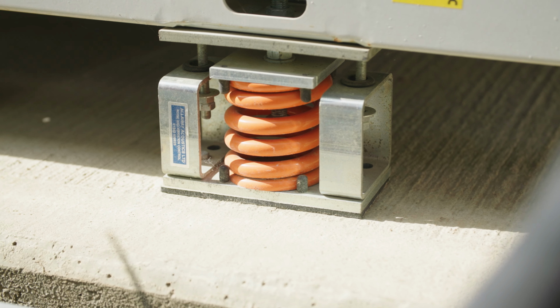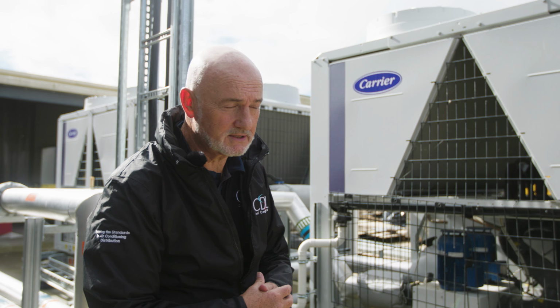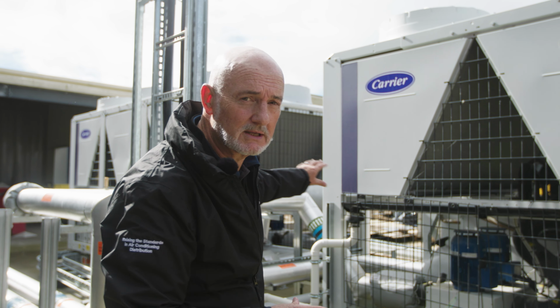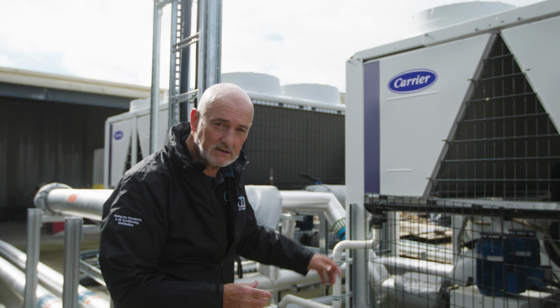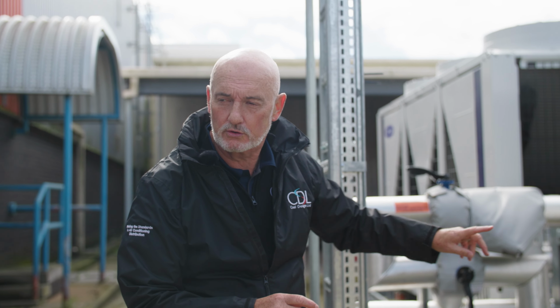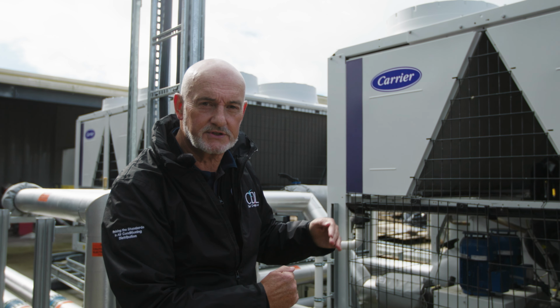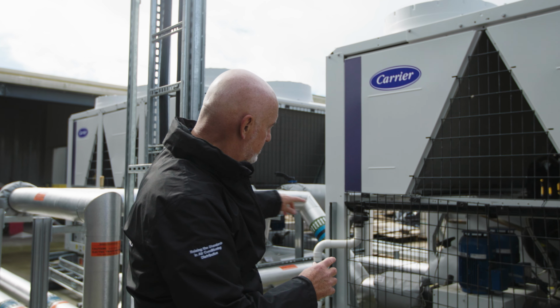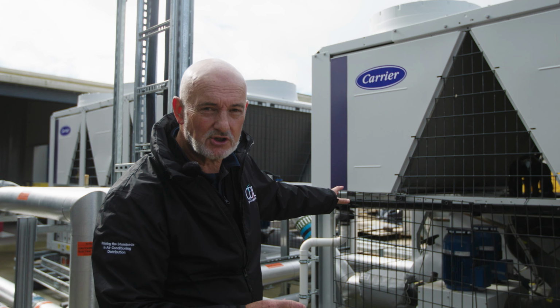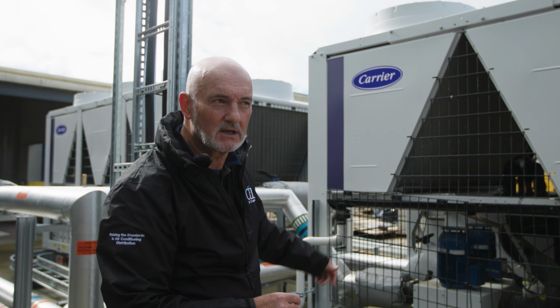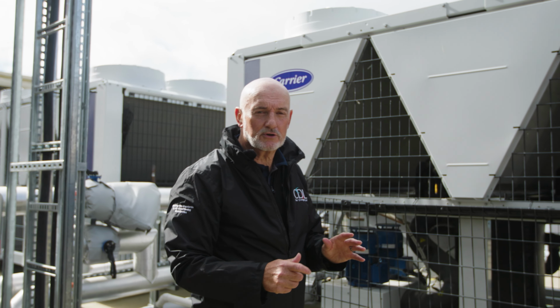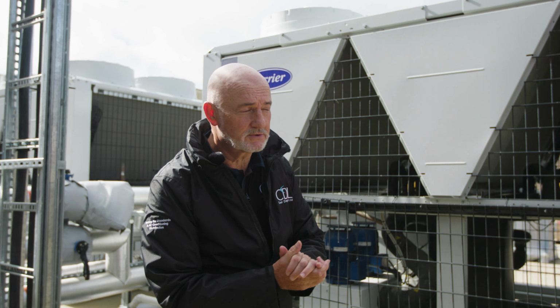The mechanical system, the water-based side of the system, which the mechanical contractor usually installs, has various valves. One of the valves you might see looks a bit like a steering wheel. That is just to commission and balance the water flow such that the exact amount of water goes through to get the temperature difference that you need. So that whole water system is balanced, and it's a bit like a check valve, a regulating valve, just to keep it correct.